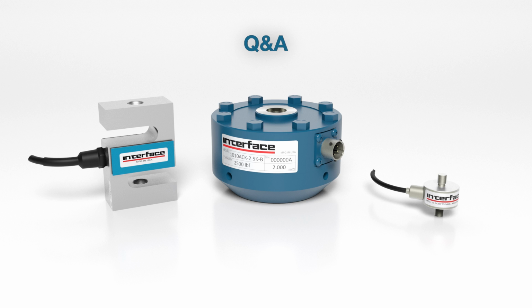You said that a mounting plate needs to have a 0.0002 inch flatness, but your slides indicate 0.002 inch flatness. Can somebody clarify which one? How many zeros does that actually need? Apologize, that could have been a typo. We need 2 10,000ths total flatness, 2 10,000ths of an inch.